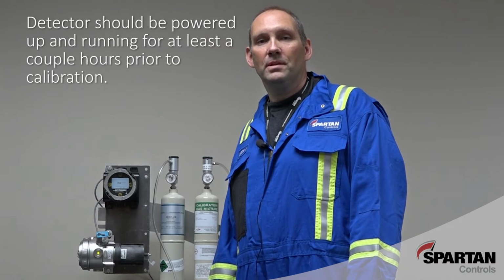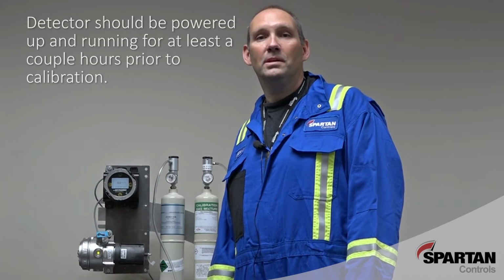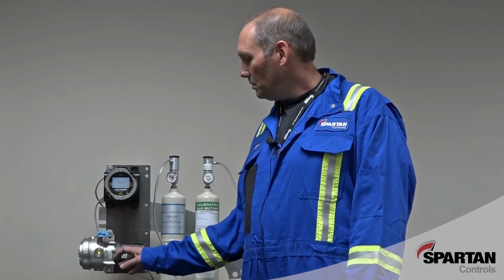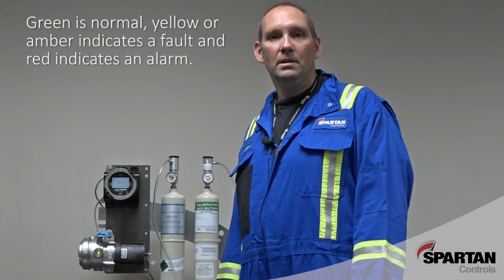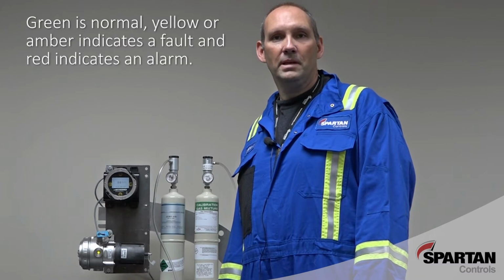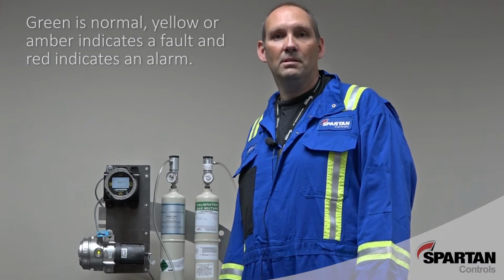Prior to doing the calibration, it's recommended by the manufacturer that the device has been powered up and running for at least a couple of hours. This ensures the device gets up to operating temperature and gets accustomed to its new environment. As you can see here, once the device is powered up and has gone through its warm-up stage, a green LED appears. This LED will change state depending on the status of the device. Green is normal, yellow or amber would indicate a fault, and red will indicate an alarm condition.